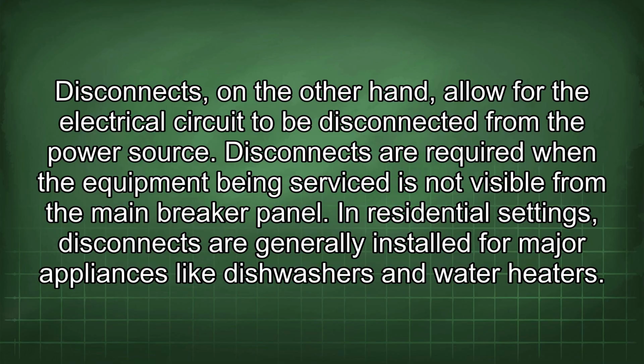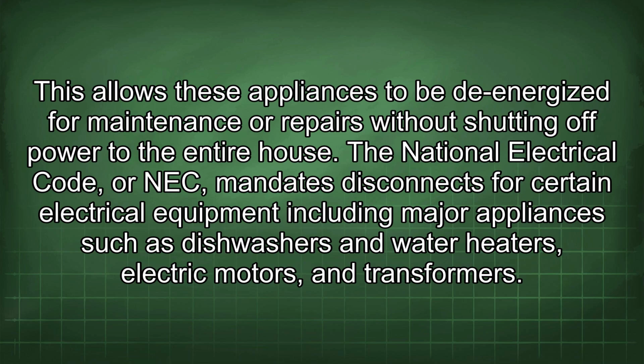In residential settings, disconnects are generally installed for major appliances like dishwashers and water heaters. This allows these appliances to be de-energized for maintenance or repairs without shutting off power to the entire house. The National Electrical Code, or NEC, mandates disconnects for certain electrical equipment including major appliances such as dishwashers and water heaters, electric motors, and transformers.